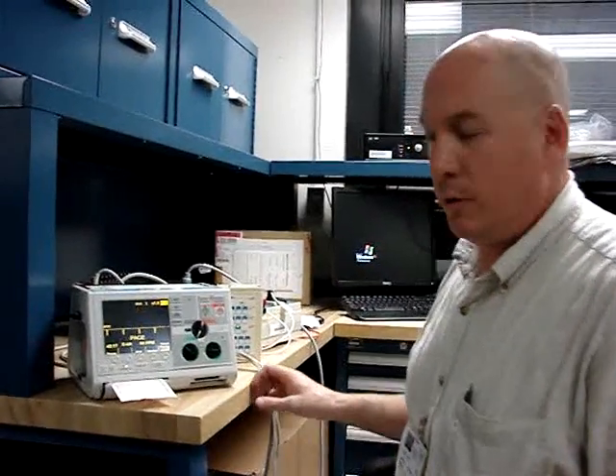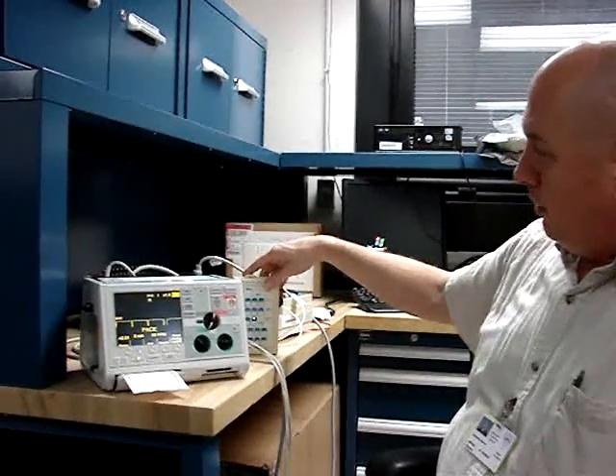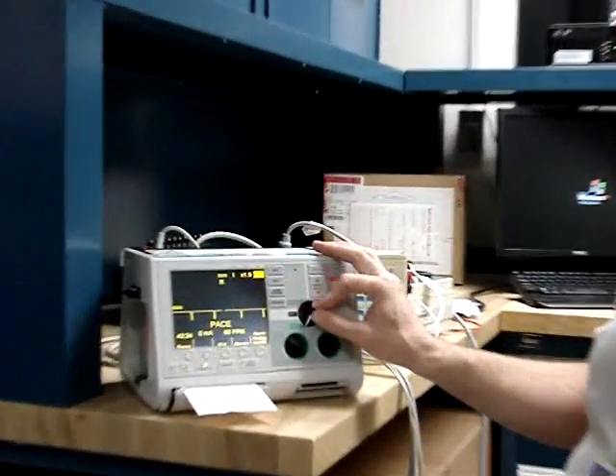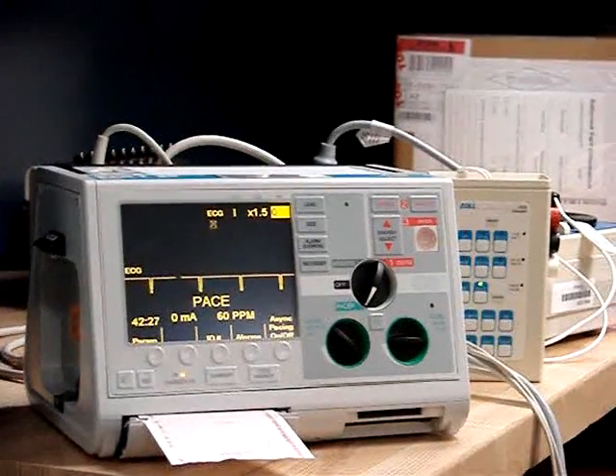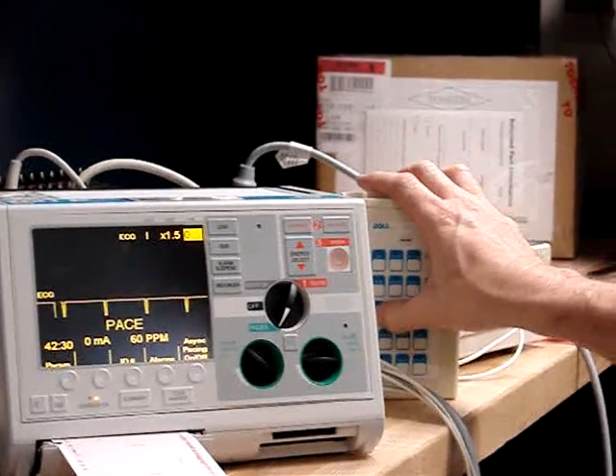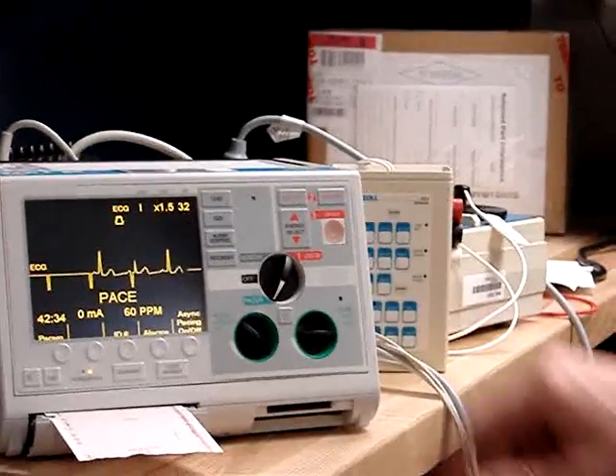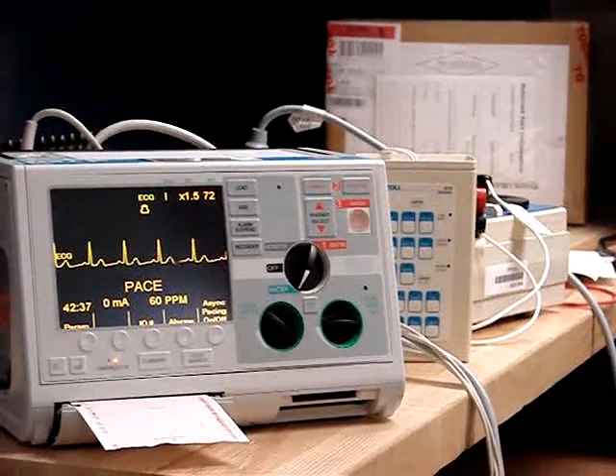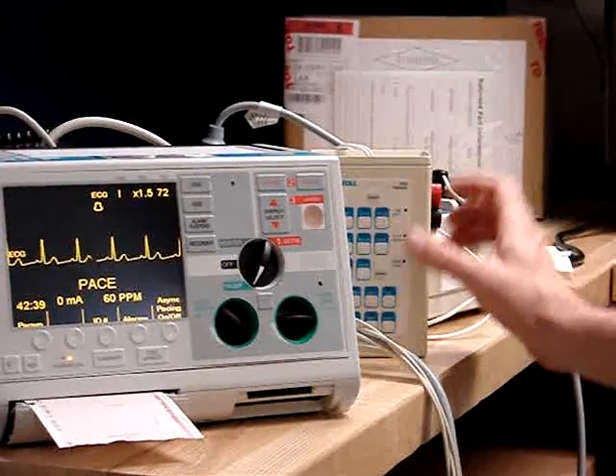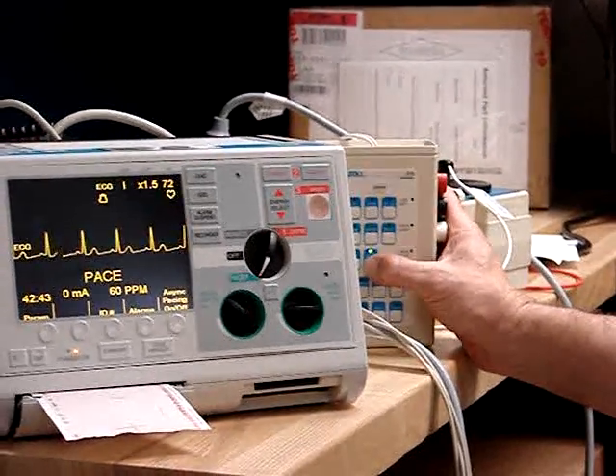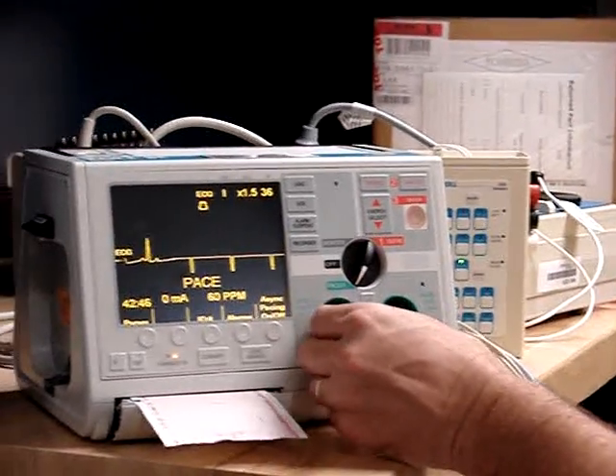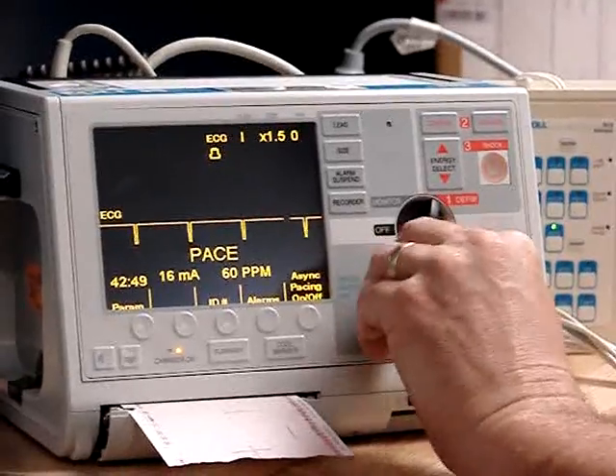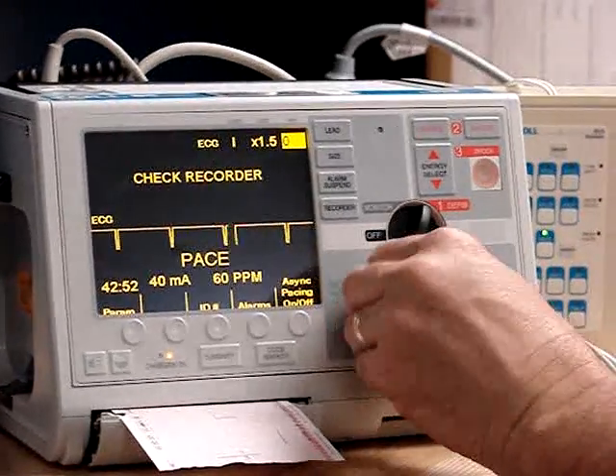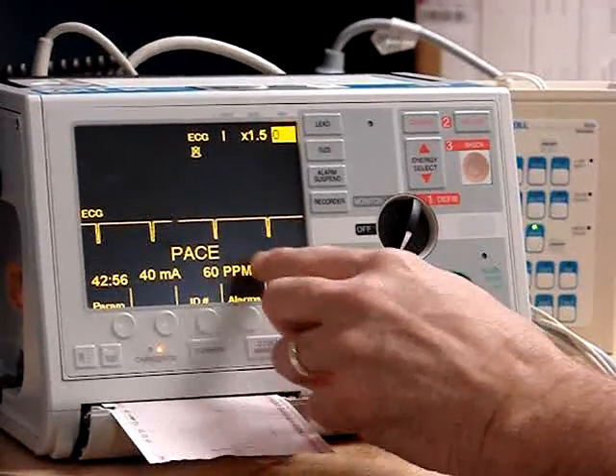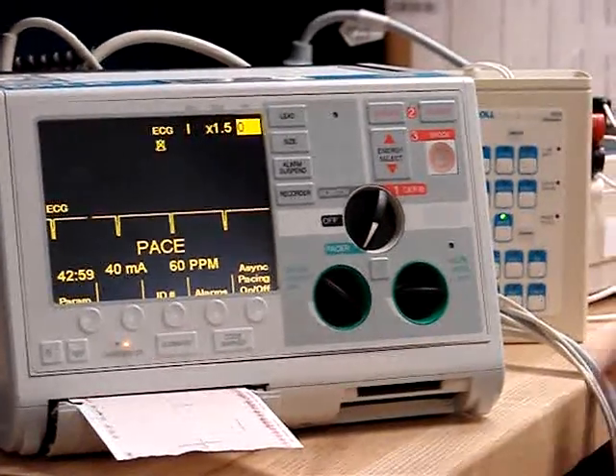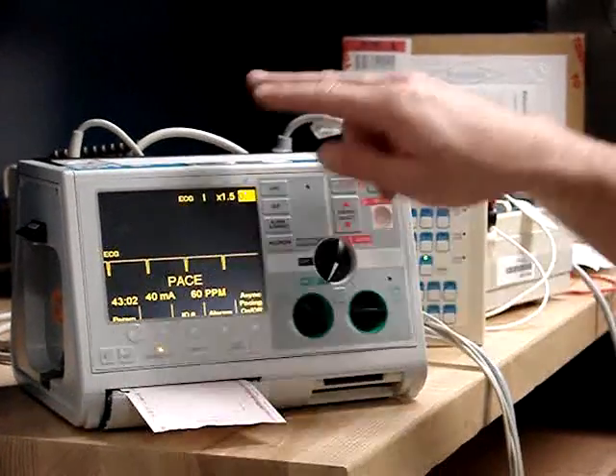Doing the pace analyzer checks, we first have to take the ECG leads and hook them to the simulator. We have to set the defibrillator in pacer mode, and when we set this up here and be in the normal sinus rhythm, we should be reading about 72 beats per minute, which it is. Okay, our first step then is to set this to asystole. We're going to change the pacer output to 40 milliamps and the pacer rate to 60 ppm. At this point, we're not seeing the pulse, we are only seeing the pace.